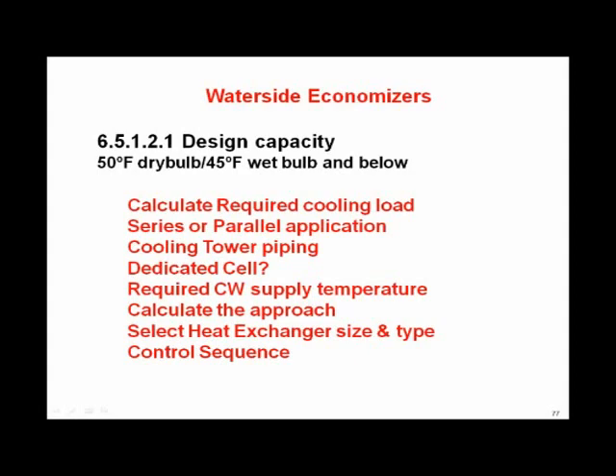What is your required chill water supply temperature? What is the approach going to be to your tower? What wet bulb are you going to size your heat exchanger and your tower on? You also have to look at the wintertime operation. You've got to look at 50-degree dry bulb, 45-degree wet bulb. That's how you're going to size your heat exchanger. And you need a control sequence.